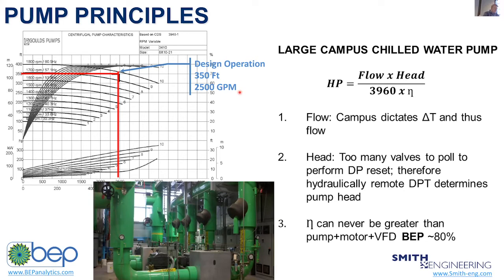But with that being the case, let's cover the horsepower equation. Horsepower is flow times head divided by a constant times the pumping efficiency. So really three things drive horsepower: the flow, the differential pressure that I have to generate, and then the pump efficiency. Looking at this example, here are my 4 chilled water pumps represented in a slightly different way. This is the efficiency. We have head and flow of the pumps. This is a snapshot, so one instant, just to drive home the example.